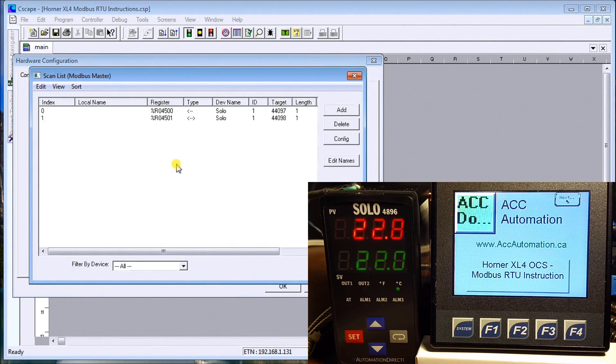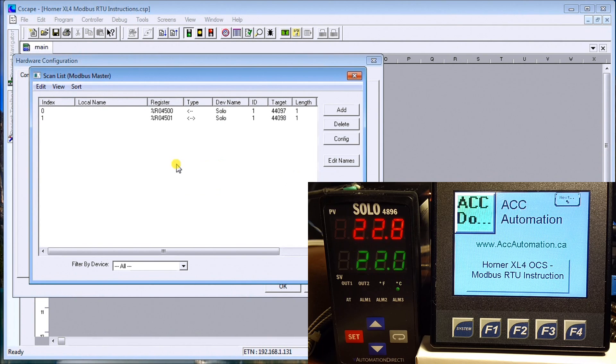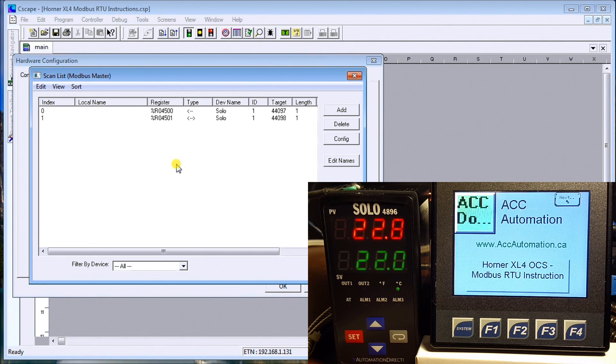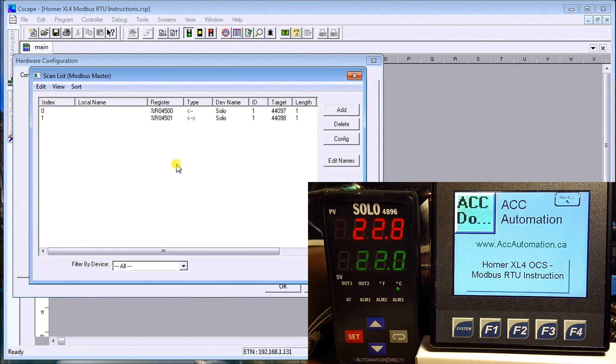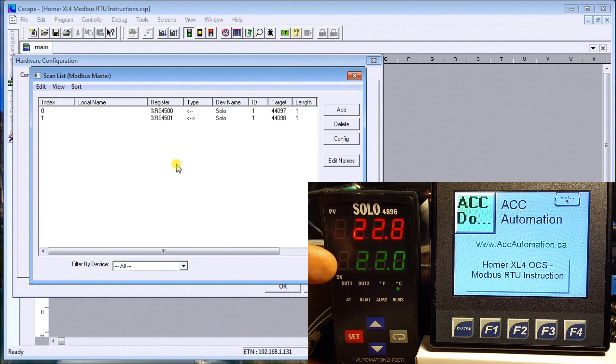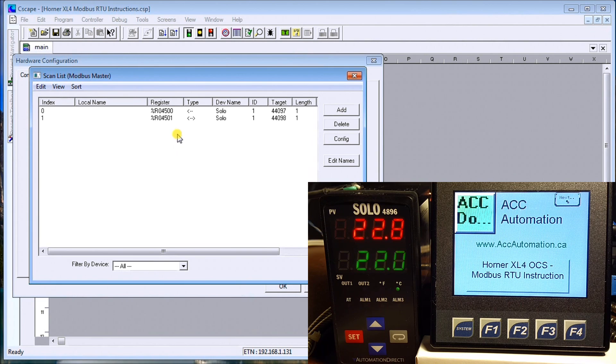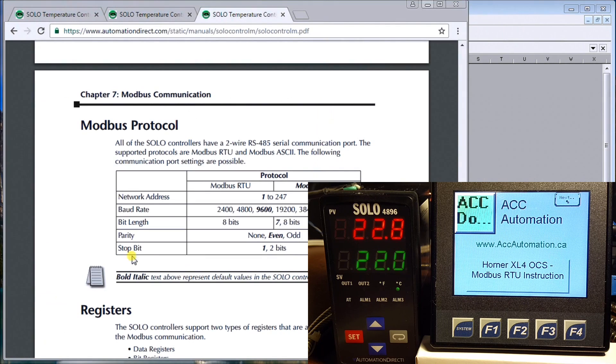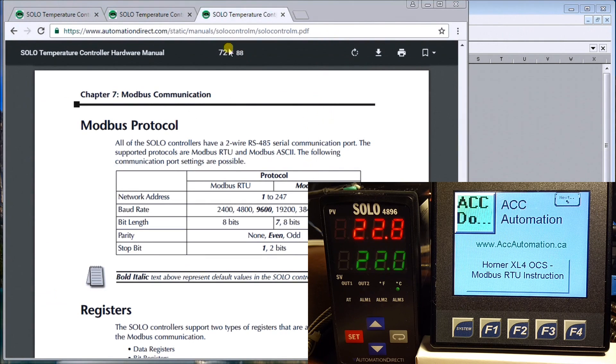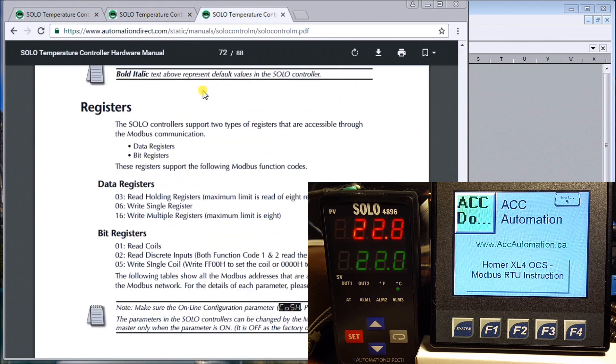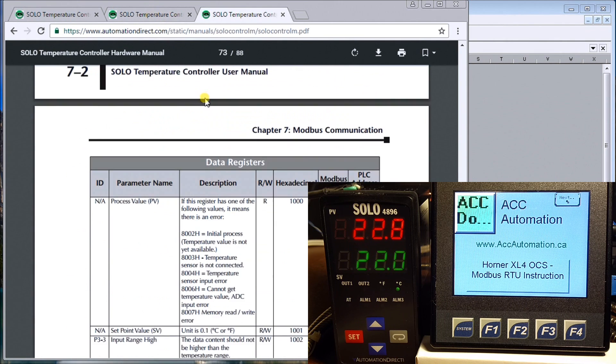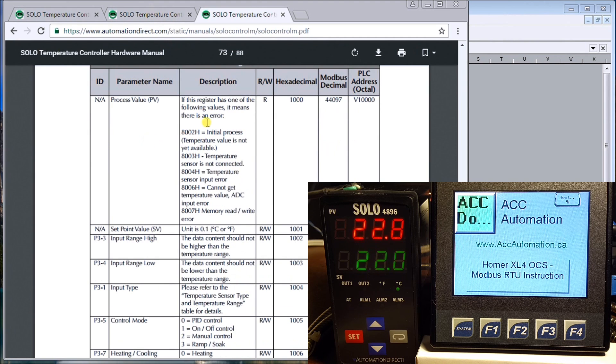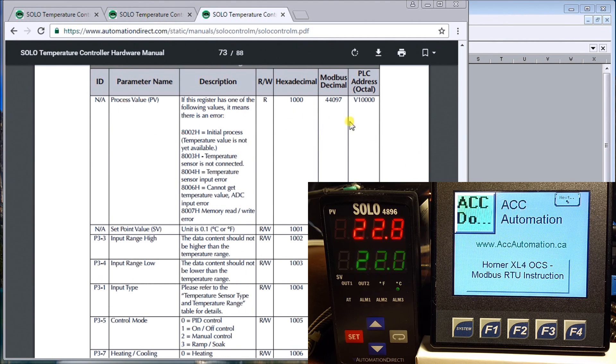Now our scan list tells us exactly what we want to scan within the SOLO unit and bring back. In our case here, what we want to scan is the process value or the present value, which is this one up here, and the set value. We want to control that set value here. If I look at my manual and scroll down, you can see here that my Modbus address for my process value is 44097.